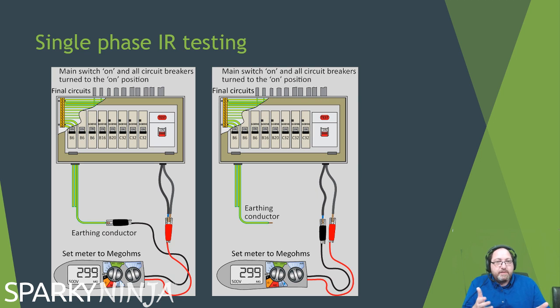The two tests that are required, illustrated here, are between live conductors, so line to neutral, and between live conductors and earth. What they're saying here is, if you do it this way, you can just do one test from line and neutral together to earth. Sometimes it's just quicker to go line 1 to earth, neutral to earth, line 1 to neutral. Sometimes it's easier to do 3 tests than set it all up to carry out 2 tests. With regards to the way you're going to do it, there could be 100 different ways, really, but see which way the assessment rig is set up. The assessment rig might be set up to encourage one way over another.